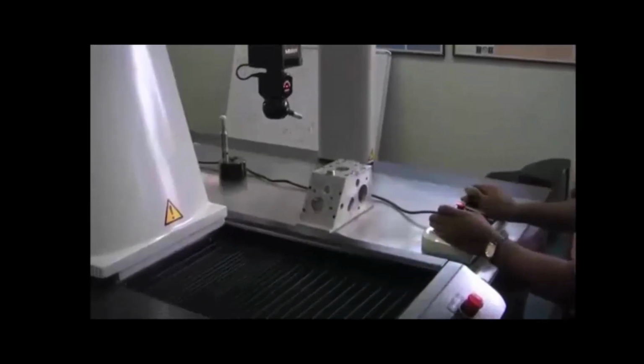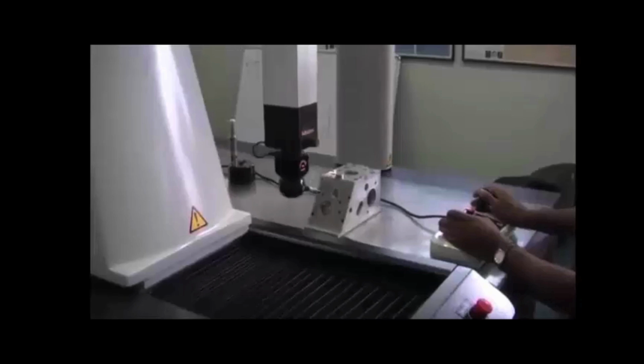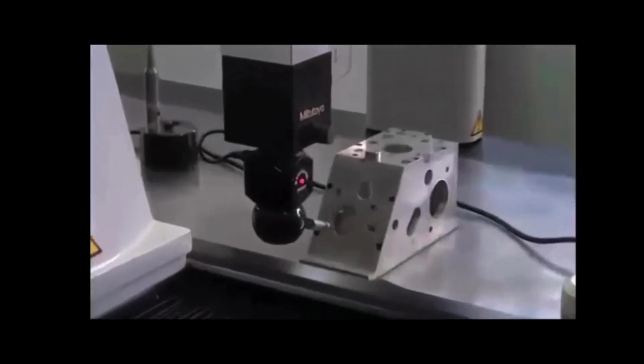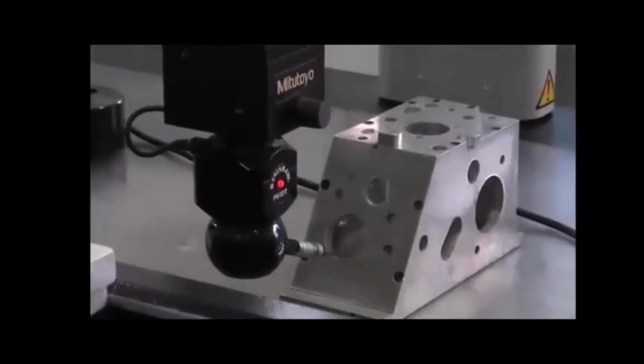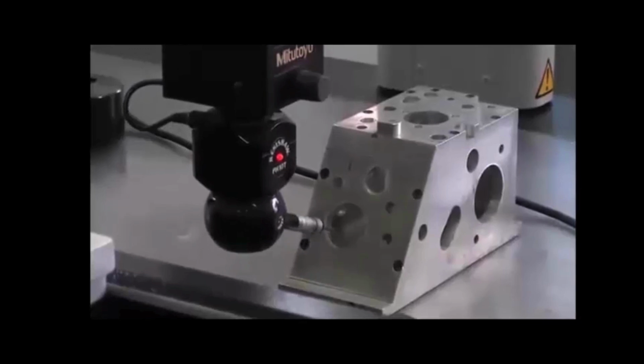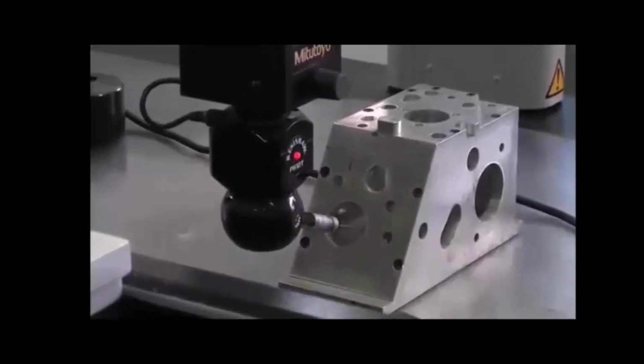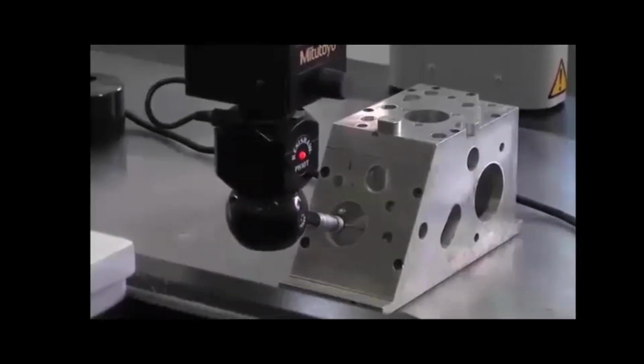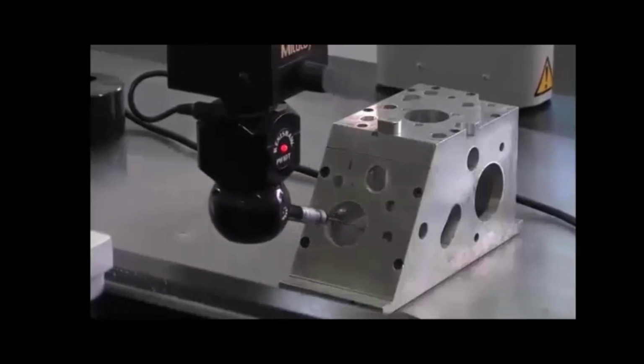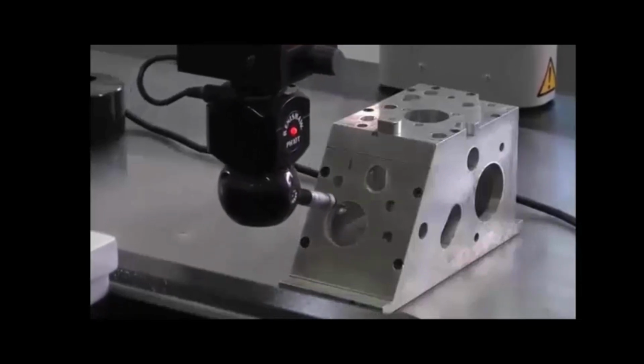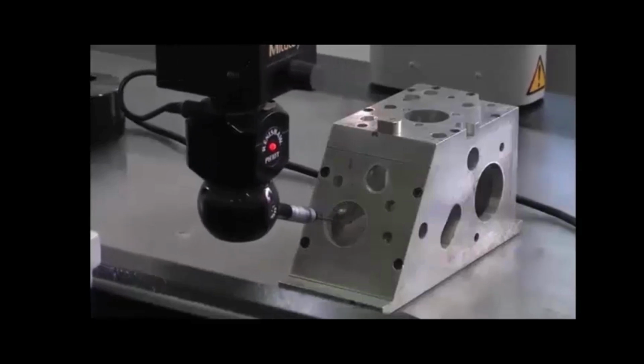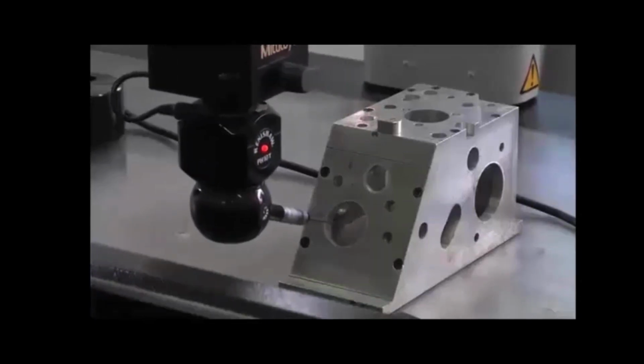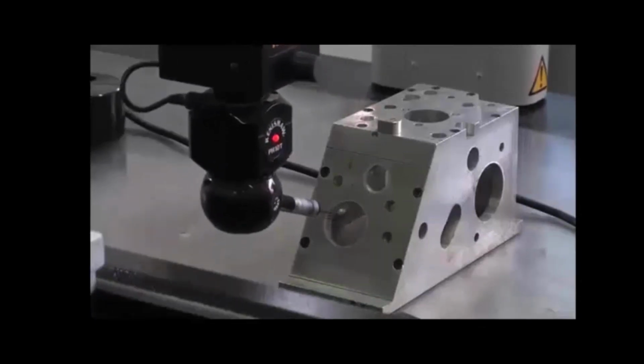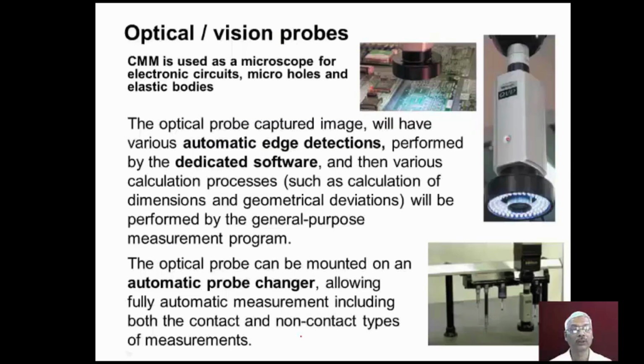And again the joystick is operated and the stylus is moved so that the stylus touches the inner surface of the bore on the inclined surface. It is contacting the inner surface of the bore. You can see the blinking of the red light. And after getting the measurement points, the software will calculate the diameter and center point coordinates.